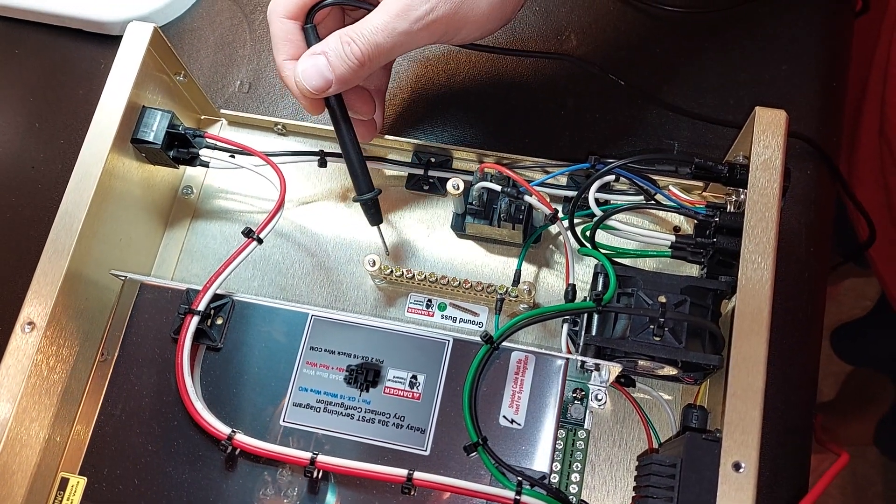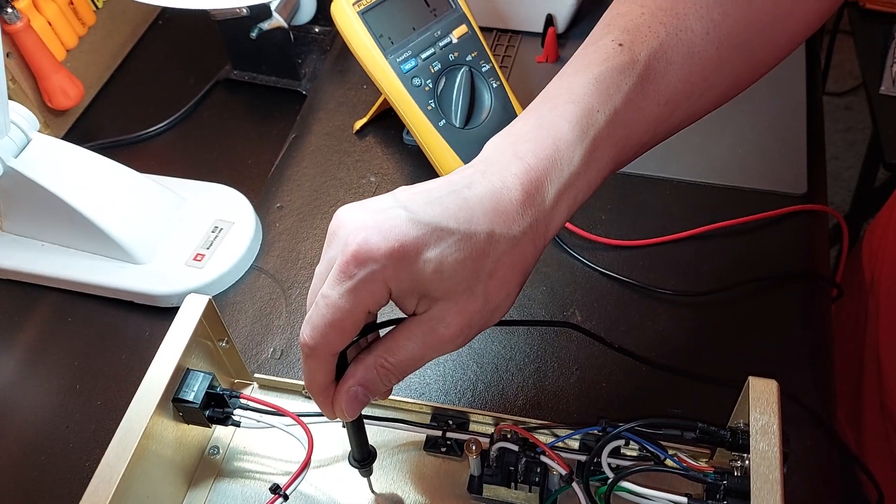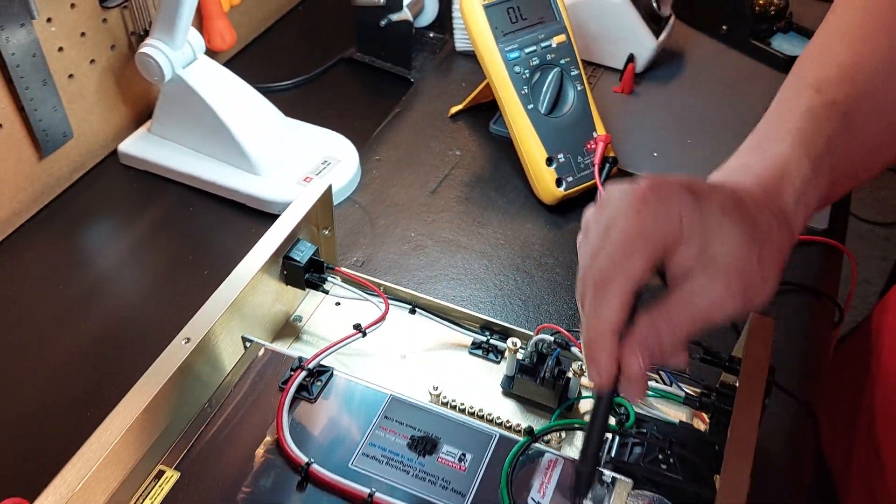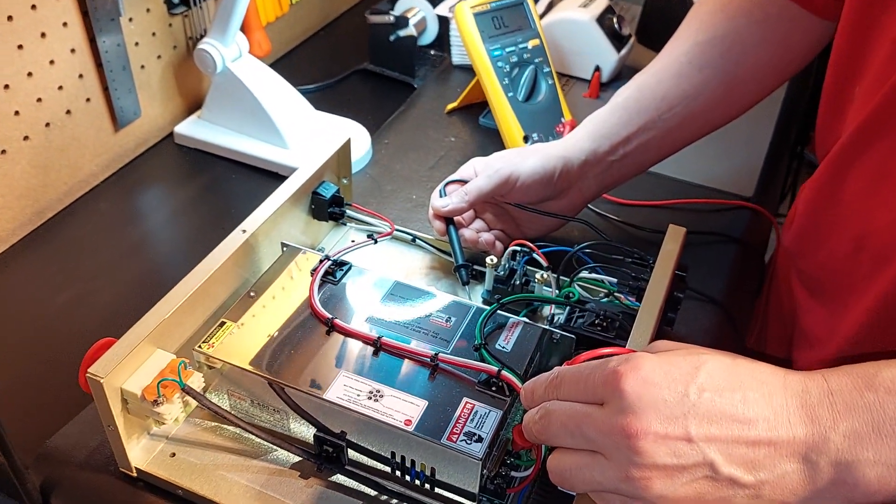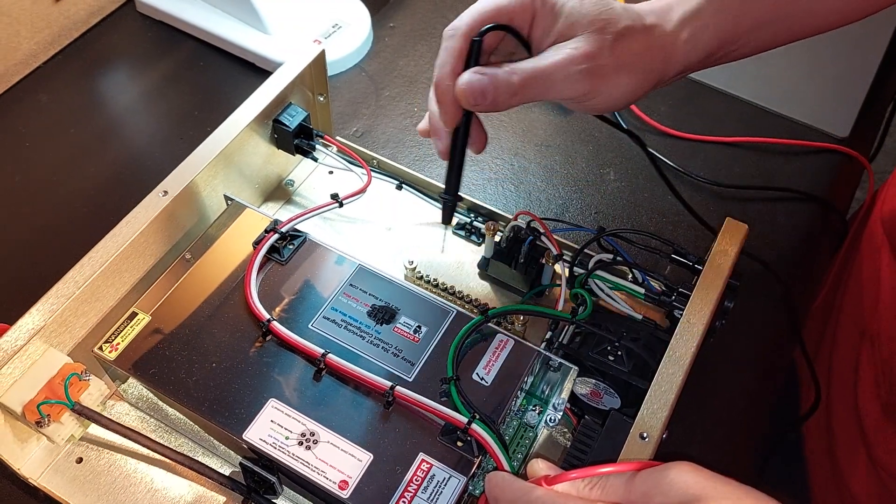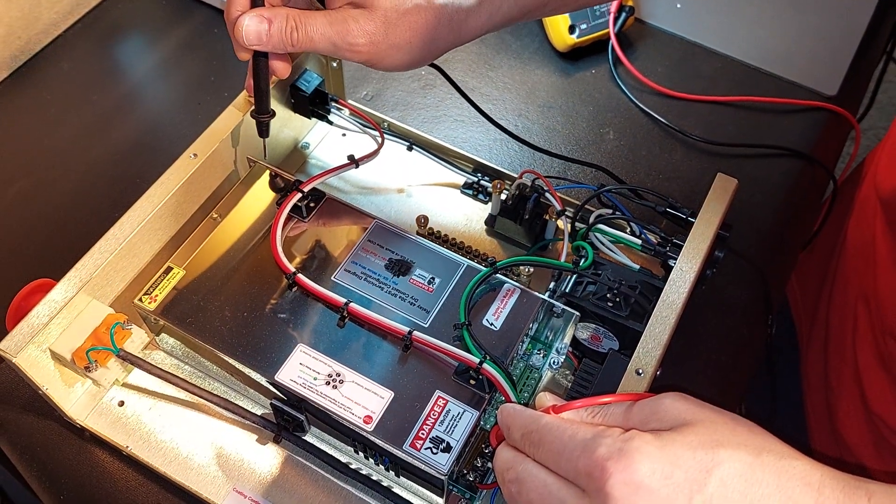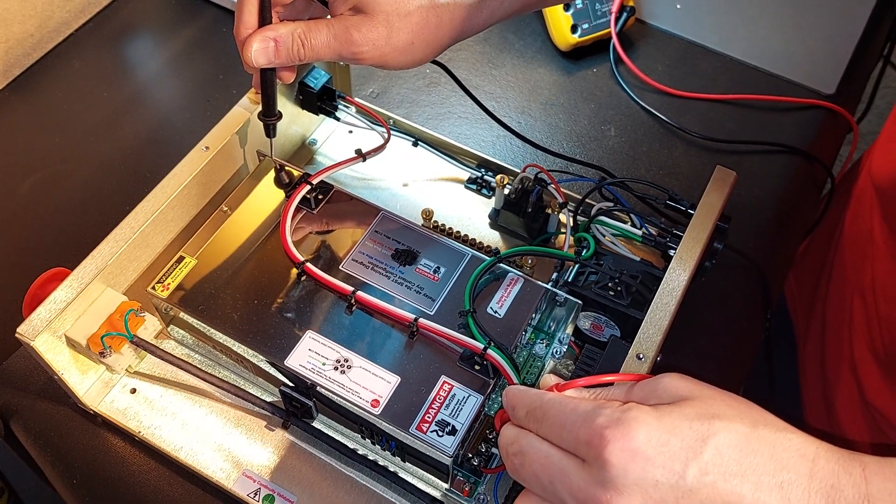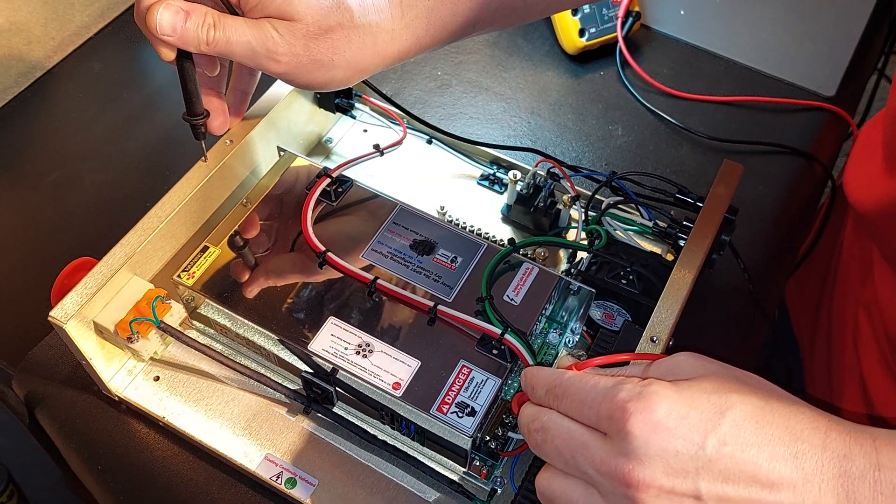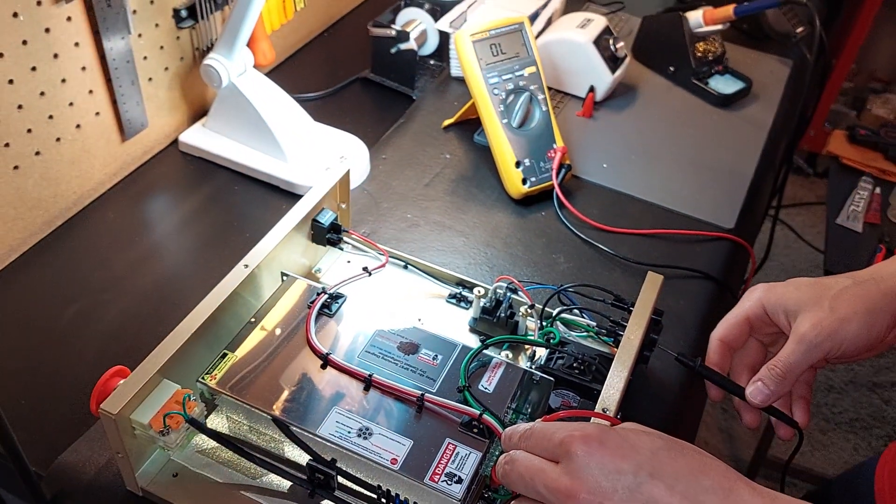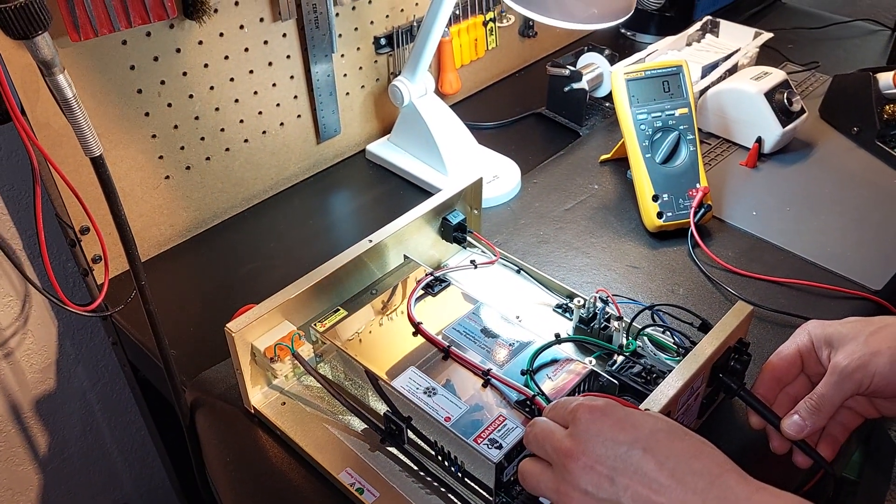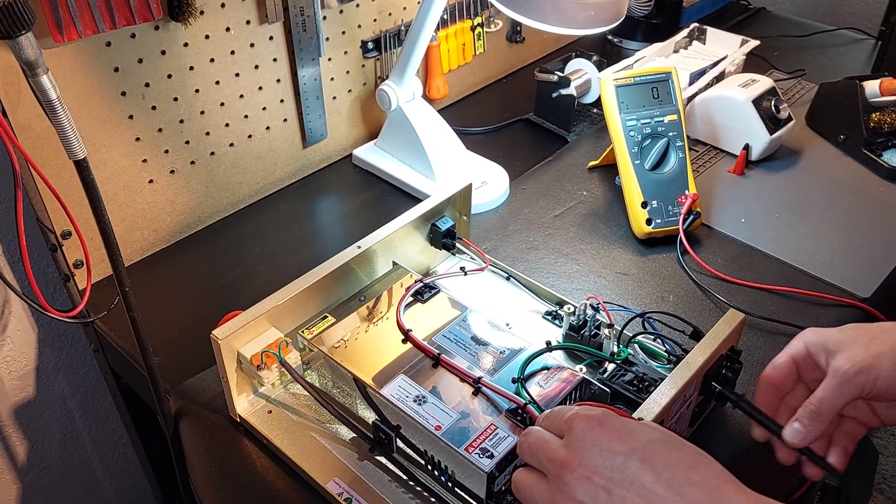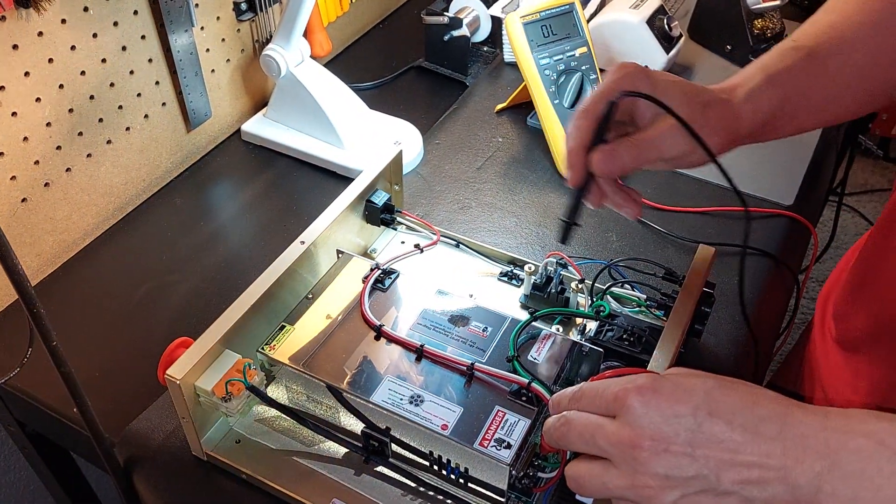Being this chassis is grounded, you can see right there we're grounded, and we're also using a ground on the power supply. This bus bar is also grounded through conduction. That means whatever touches this chassis, whether it be the power supply, I'm actually doing the power supply chassis at zero, the electrical chassis, that's at zero. Everything that's touching that, including the ground on the auxiliary port, is also going to register zero. They're all interconnected, and they're not connected through this bus bar, but it's how the wiring is done.